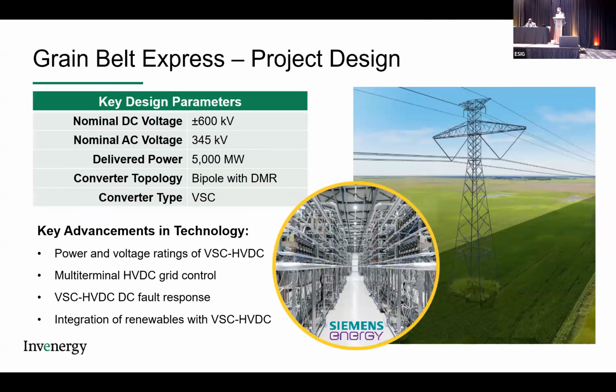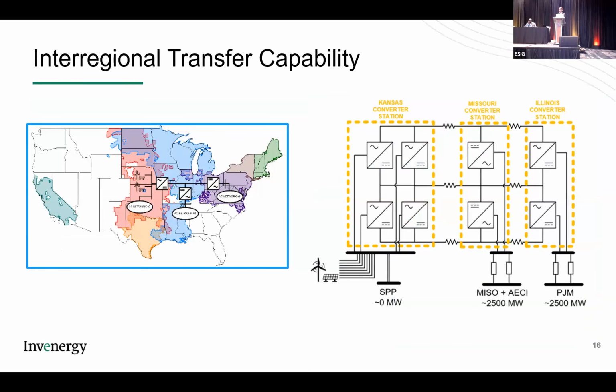Looking at the technology, Grain Belt has gone with a 600 kV bipole HVDC configuration, with 345 kV AC interconnections on each side, rated to deliver 5,000 megawatts of power. There's a set of about 2,500 megawatt converters, two in parallel on the sending side, so you get a 2,500 megawatt delivery into Missouri and a 2,500 megawatt delivery into PJM. These are fundamental design decisions that are crucial in the early stages.